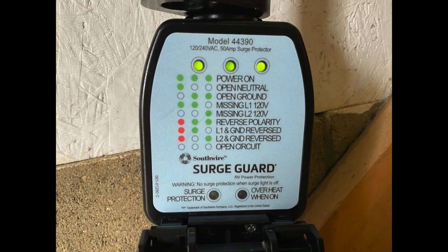I turned the breaker on and off a couple times to figure out the exact problem, and everything came back on and looked good. I notified the park and they came out. They determined that the circuit breaker inside the pedestal had gotten warm before and had a loose connection. If I had just plugged in my surge protector and seen all green lights, I would have thought the power was good, but it was actually fluctuating, going on and off. I wouldn't have known it.